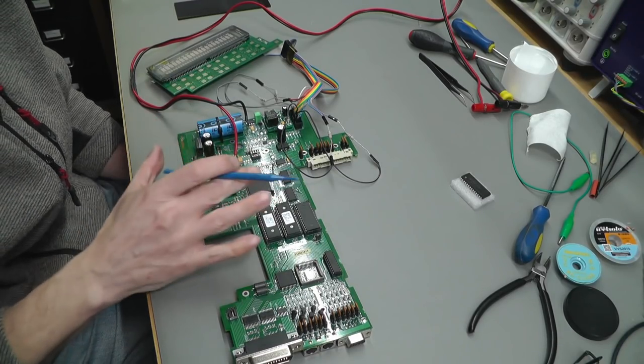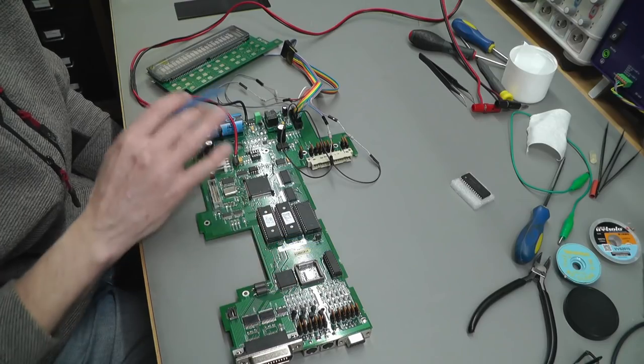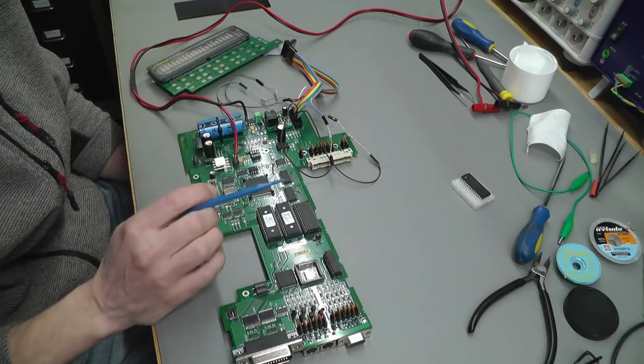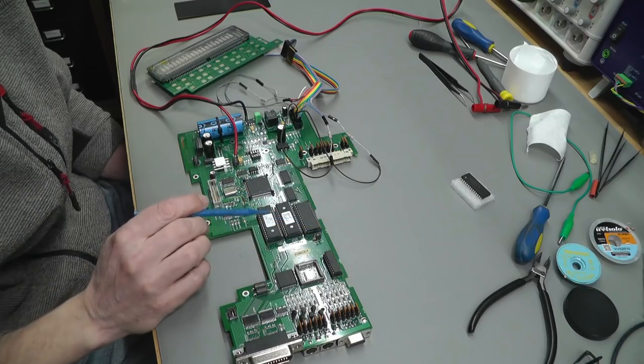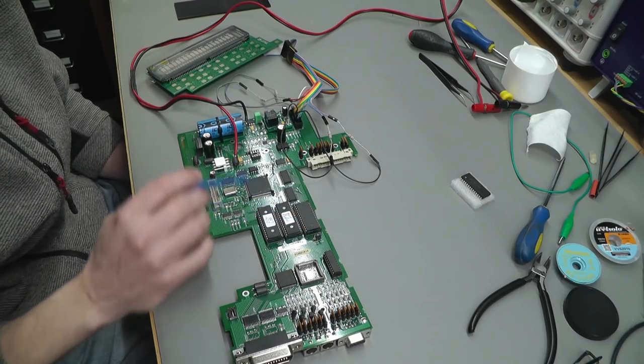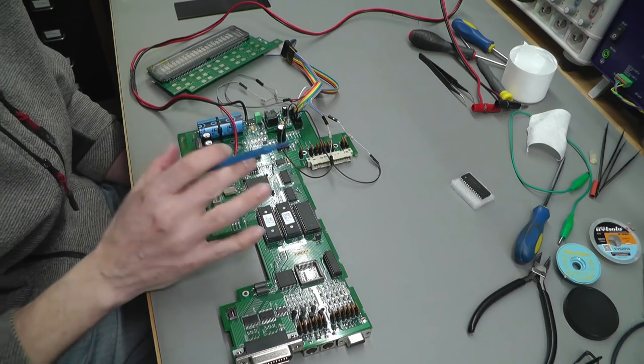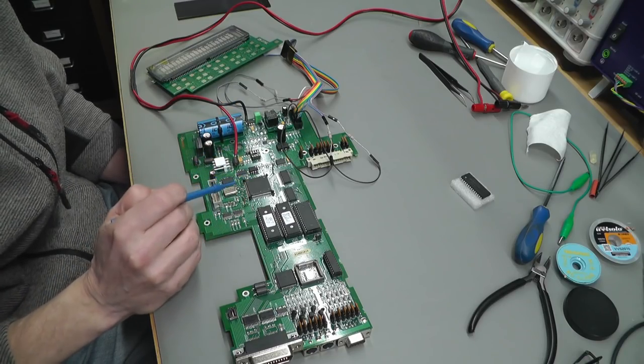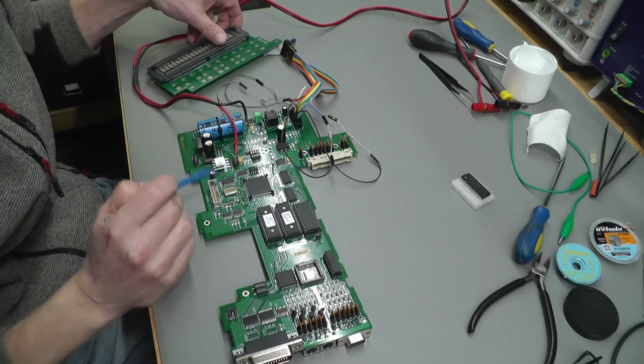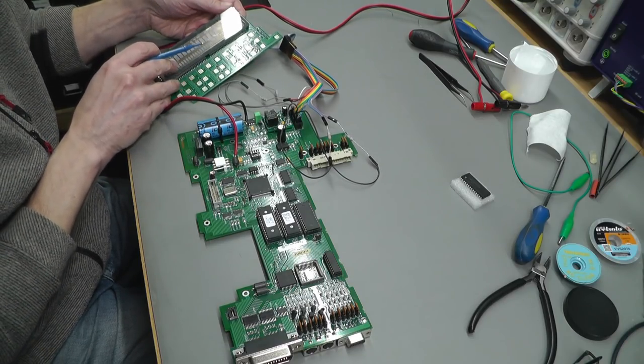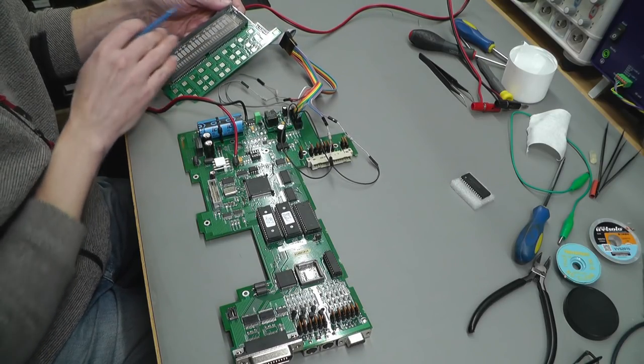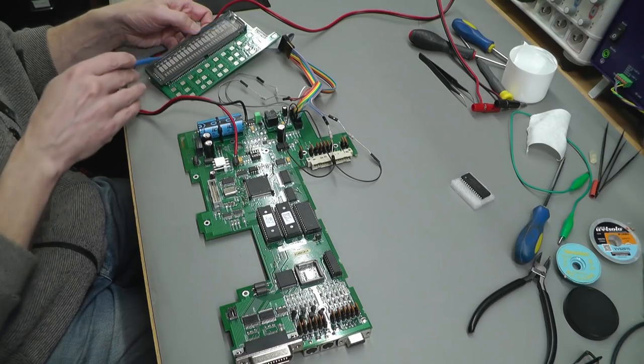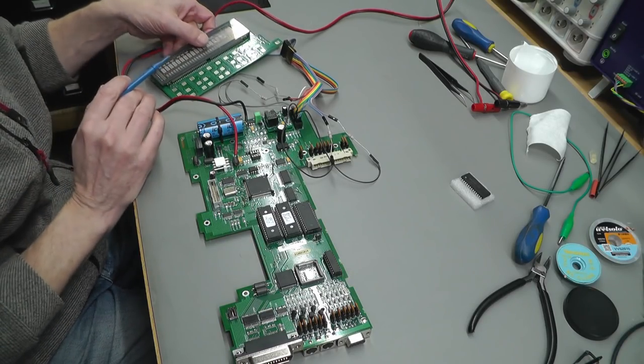You saw me in part two change out quite a number of ICs, fix the high voltage board. We did quite a lot, even burning new PROMs for the actual firmware, so a lot of repairs were done to the hardware of the digital board. Then we went on to connect up the display board.